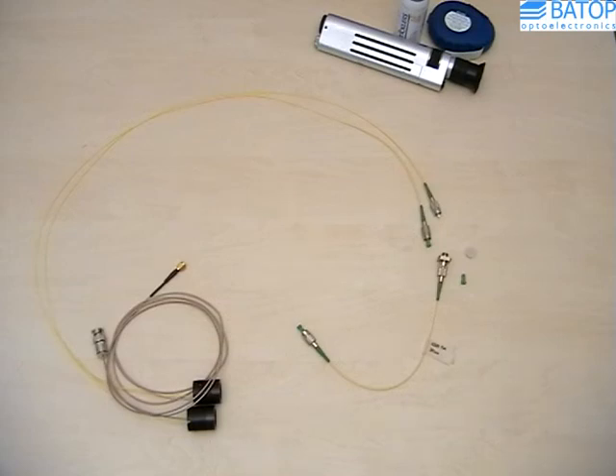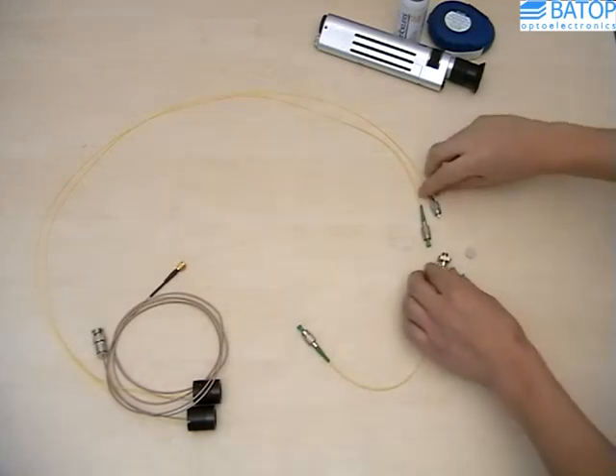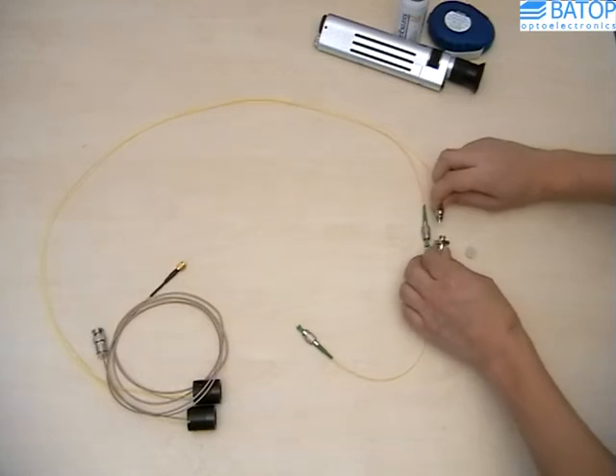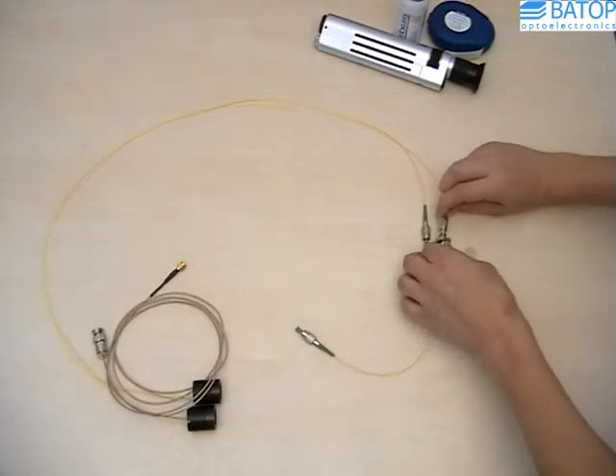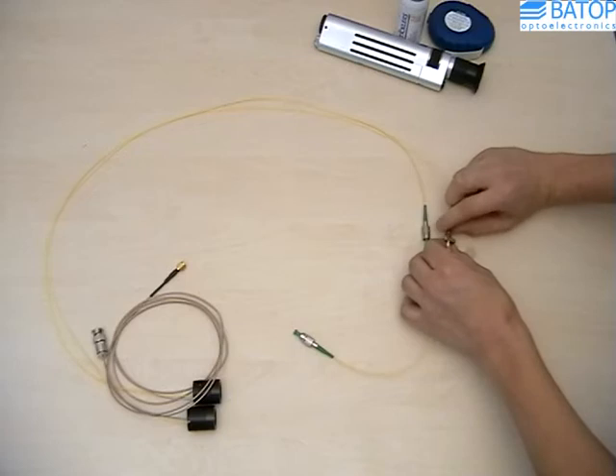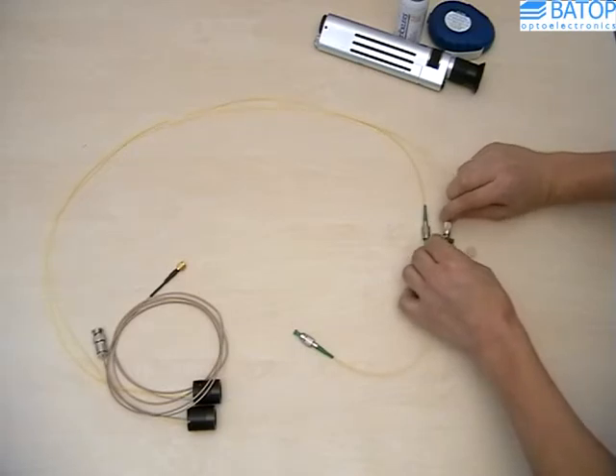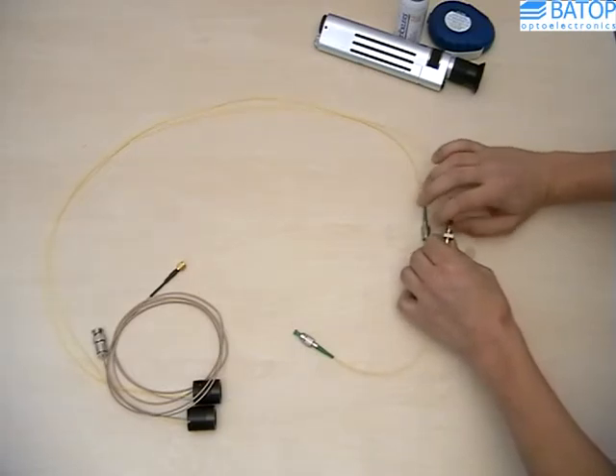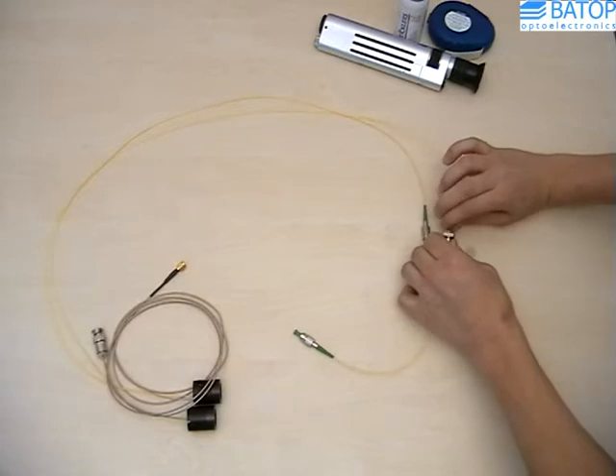The temporal tuning between the laser pulses on the emitter and the detector is done in two steps. First the fiber cable on the emitter side is extended by a patch cable corresponding to the optical length of the TeraHertz beam path. If so the TeraHertz pulse hits the detector right at the moment it is gated by the detector laser pulse.